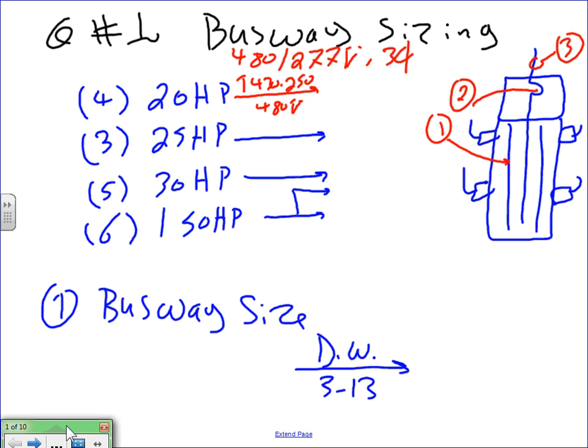Okay, so let's go ahead and start. The first thing, guys, is question number one will be about busway sizes. It could be a plug-in busway, a feeder busway, or a trolley busway. The calculation really wouldn't make a difference. In this case, most likely it's going to be a plug-in because we have equipment to plug it in. In this case, I have four motors or four machines. Each one of them is 20 horsepower, 25, 30, and 150 horsepower each. I need to size first the busway itself, the overcurrent protection device, and the feeder that feeds the busway. Three things I want to size for this system: the actual size of the plug-in busway, the overcurrent protection device that will take that baby, as well as the feeder that feeds it.